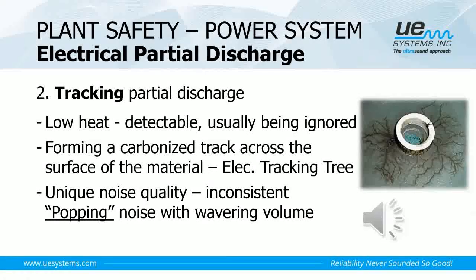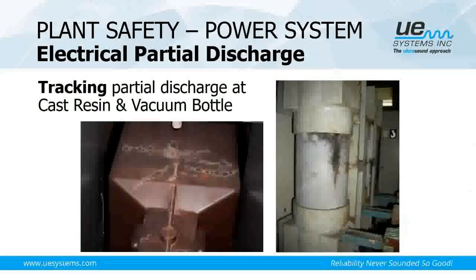Secondly, tracking partial discharge. We can categorize it as cancer level 2. It has low heat, detectable by infrared thermography, but usually ignored because the temperature difference is too low. It forms a carbonized tracking tree at the surface. The unique noise quality is an inconsistent popping noise with wavering volumes. This is an example of tracking partial discharge found at cast resin and vacuum bottles.